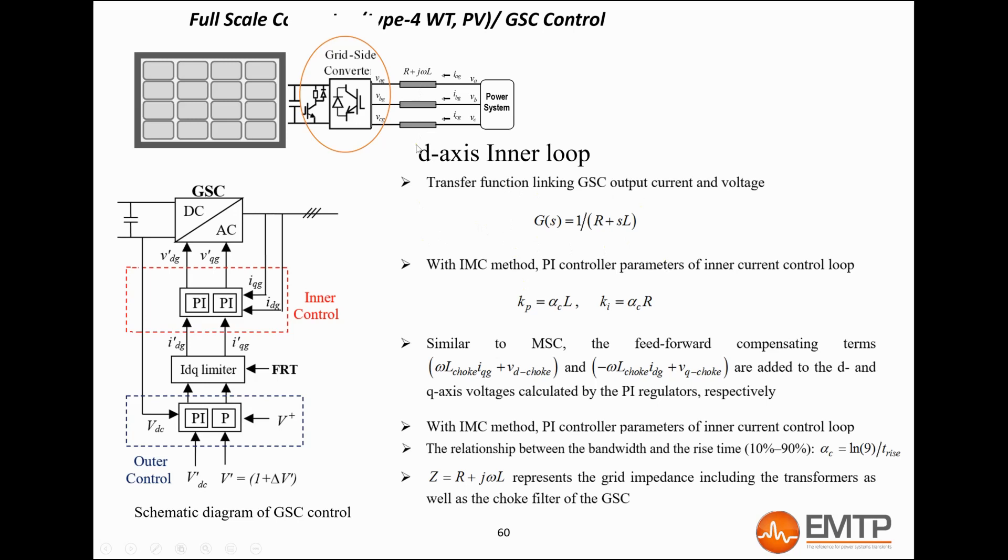where R and L are the resistances and inductances of the filter choke, the converter transformer, the park transformer, and the grid-side impedance combined. In the generic model mask, the user can set the rise time, which determines the inner loop speed. It is typically set to 10 ms.